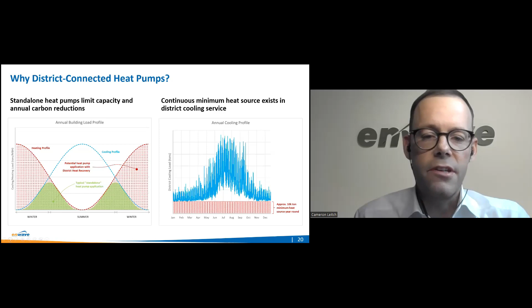If instead that customer can access the heat source created by other district energy customers with year-round cooling loads, a local heat pump plant can be sized for greater than the coincident heating and cooling peak of the building, allowing the customer to tune the plant size to meet their carbon targets, up to and including their entire heating load, the area under the red curve. The graph on the right represents Enwave Toronto's cooling load over a typical year, and it reflects a minimum heat source for district heat recovery of approximately 10,000 tons. Next slide, please.